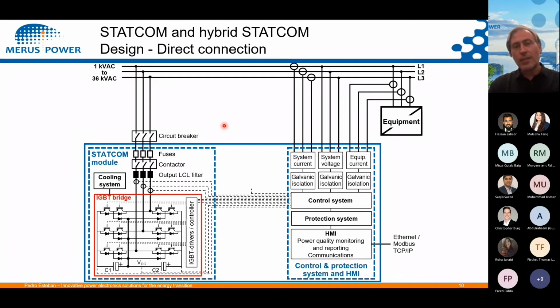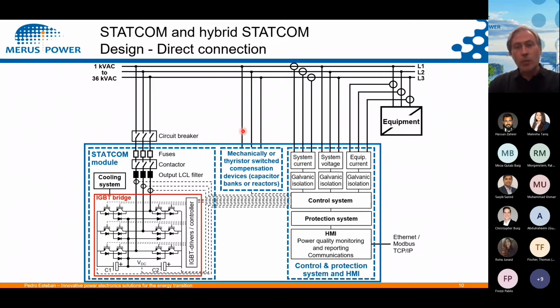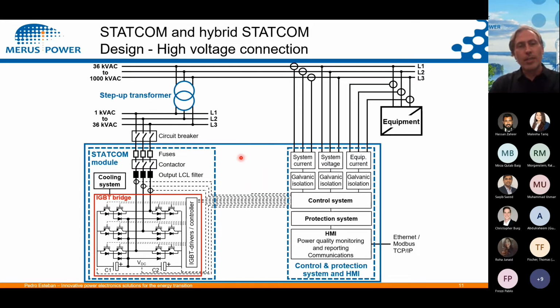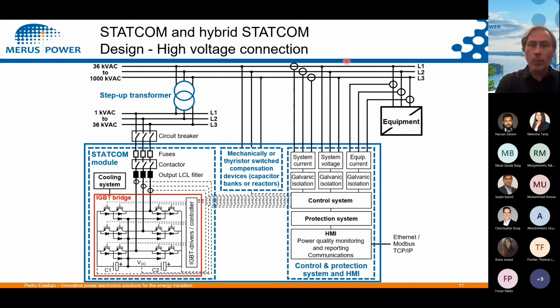This is a STATCOM. The difference with a hybrid STATCOM is only that the hybrid STATCOM will also have, working together or controlled by this control system, mechanically switched, typically by circuit breaker or contactor, or thyristor switched, capacitor banks or reactor banks. If we want to connect these devices to voltages over 36 kilovolts, the easier solution is to use a step-up transformer. We take the signals anyway from this voltage level. Again, a hybrid STATCOM will just have this kind of capacitor bank or reactor bank working together with the STATCOM modules.